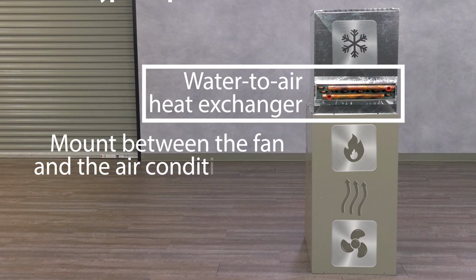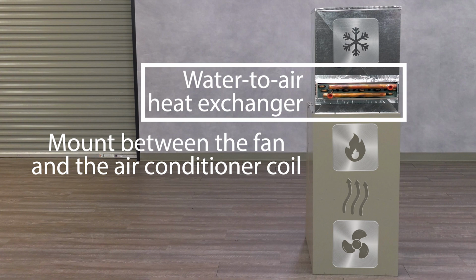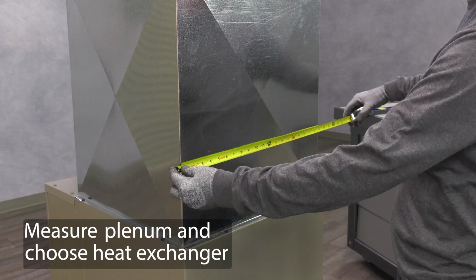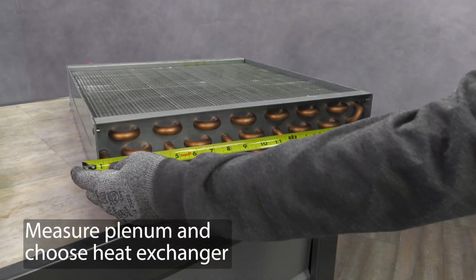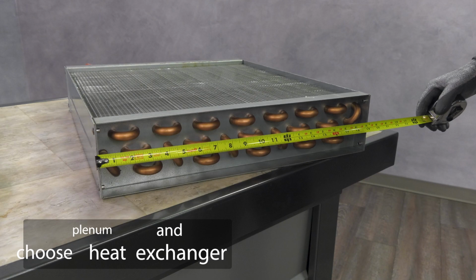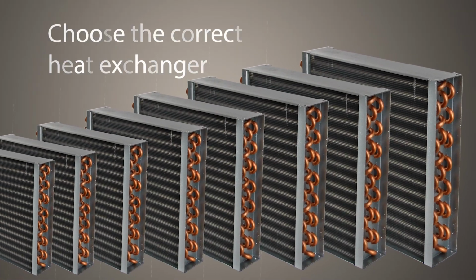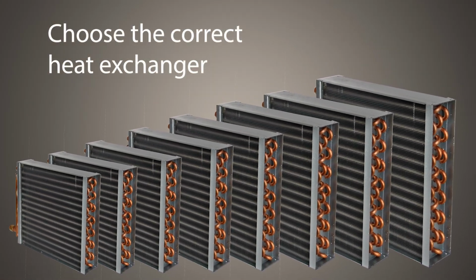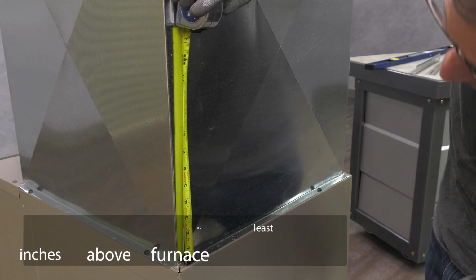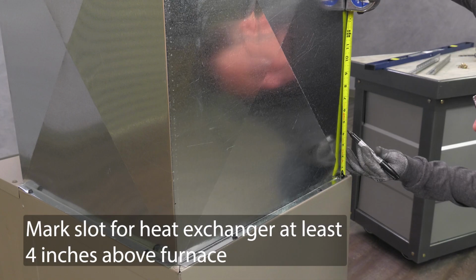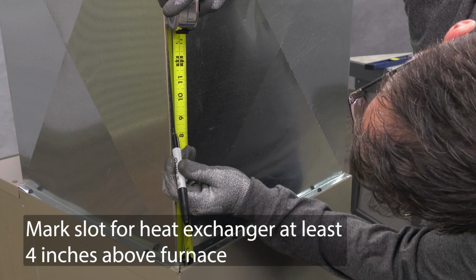Mount the heat exchanger between the fan and the air conditioning coil so the heat exchanger will not freeze when the air conditioner is being used. Measure the furnace plenum on the installation side and choose a water-to-air heat exchanger that fits correctly. We offer many different sizes of heat exchangers to fit your application. Measure up at least 4 inches from the top of the furnace and mark 4 spots for reference points.